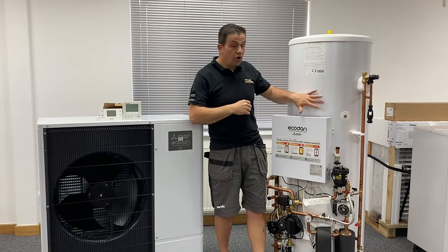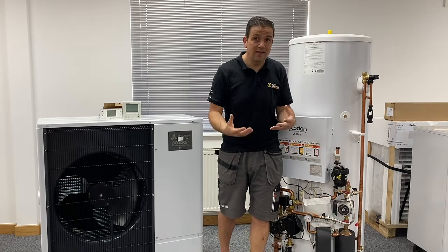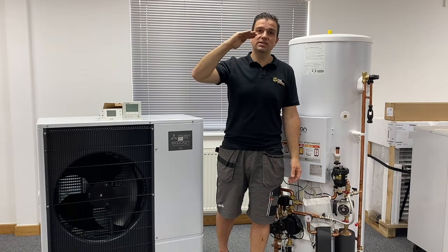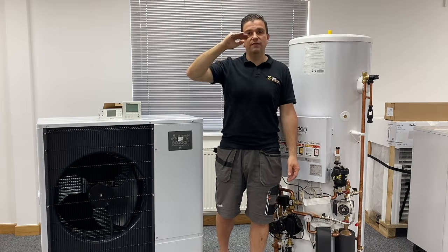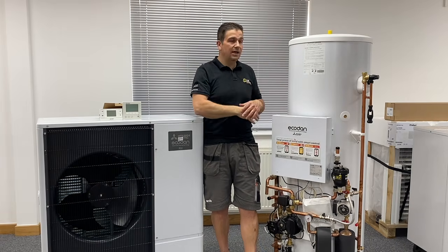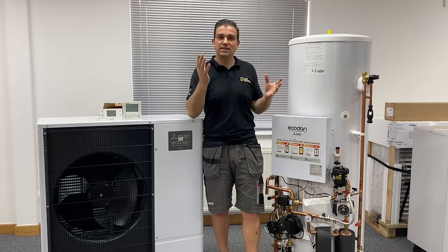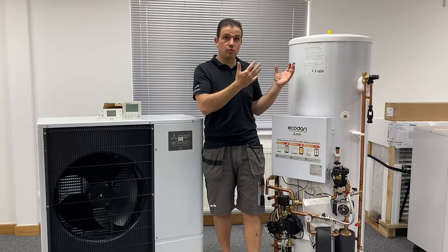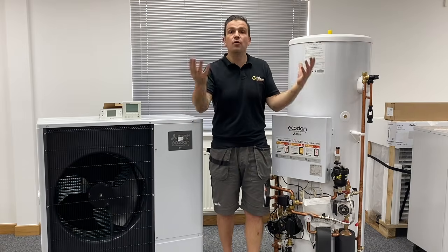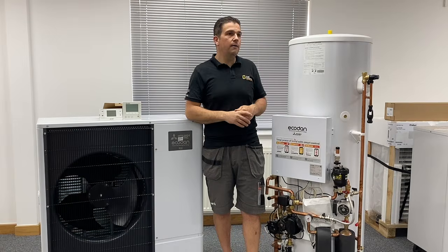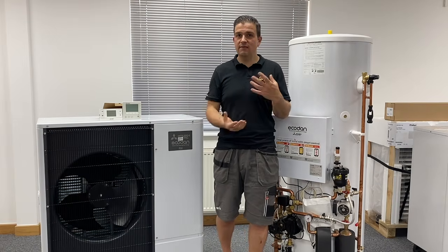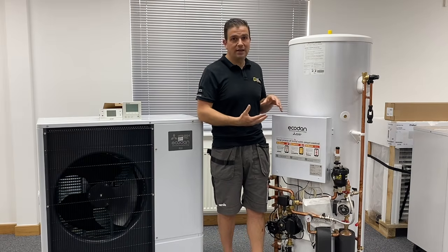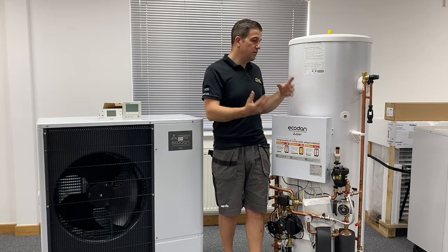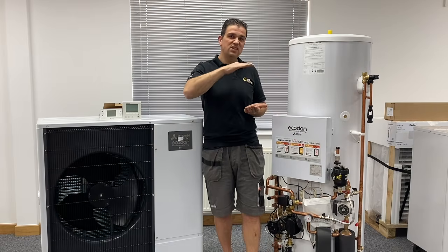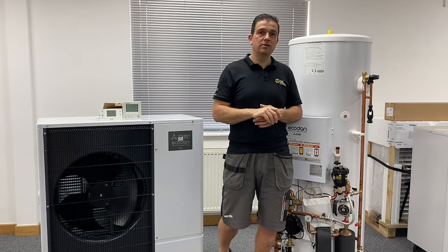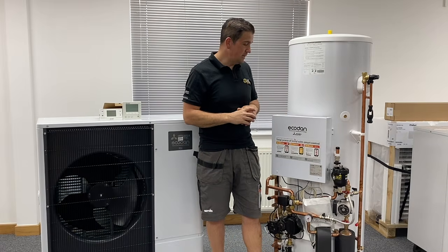And then the internal immersion for this cylinder will then kick in, take it and bump it up to that other temperature, make sure it sits there, so it might come on and off a little bit if it starts to fall, or during that cycle you might end up using it. I mean, we try to set the program in the middle of the night, but if it was in the daytime, or you might have, say, a tariff that works better on a Sunday afternoon, or you might well have something linked up to a solar PV system, then that will enable us to control that, put the Legionella procedure on, and then that will sit there for the 3 hours in which we can determine that the bacteria is eliminated.